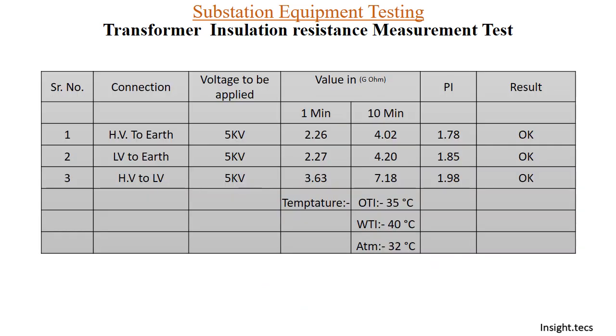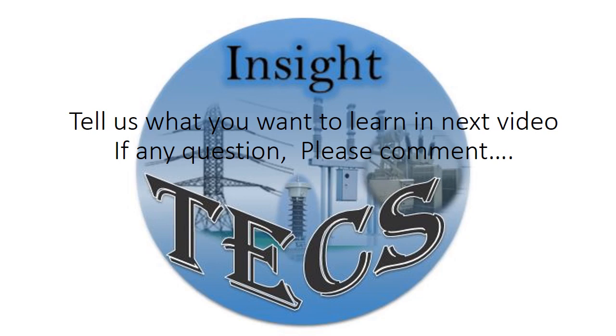All readings for HV to earth, LV to earth, and HV to LV have been compiled — applied voltage, values at one minute and ten minutes — and based on those we calculated the PI (polarization index). It is important to note that while measuring IR values, we must record the oil temperature, winding temperature, and outside atmosphere temperature, because these temperatures can cause variation in the IR values and PI value. This is how you measure the insulation resistance of a transformer. If you have any queries, ask in the comment section below. Thank you.